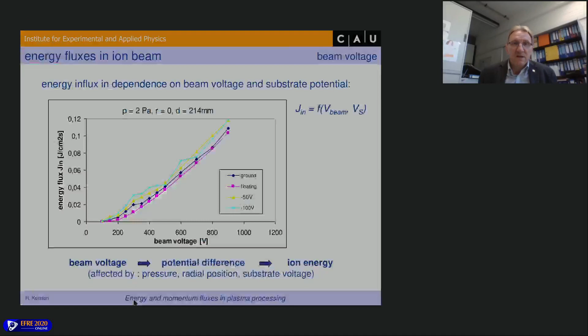And then we measured the radial profile of this ion beam, and the diameter of this ion beam is about 12 centimeters, and this is the center of the beam. And for an ideal ion beam source, you would expect a rectangular profile, but this is a real source, not an ideal. So this is the radial profile measured by our thermal probe, as you can see here.